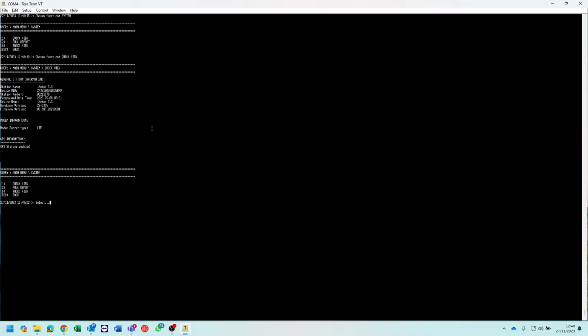This is quite useful to determine, if there's any uncertainty, the actual ID number of the DTU. There will be stickers on the exterior of the unit, there'll be stickers on the inside of the enclosure, and probably on the printed circuit board. But the 100% test as to what the number is to log into Teraterm, and this one, as you can see, is 00211C79. The relevance behind this is that we need that number from you to link it to the appropriate field that you have your DTU installed into. If a motherboard gets swapped out, the unique number is actually relating to the motherboard, and so that number could change. So just an important point.